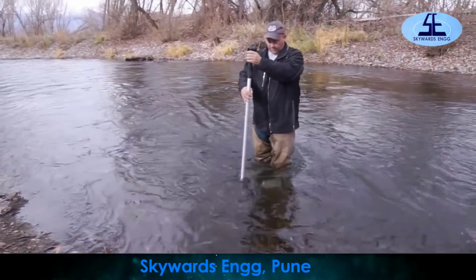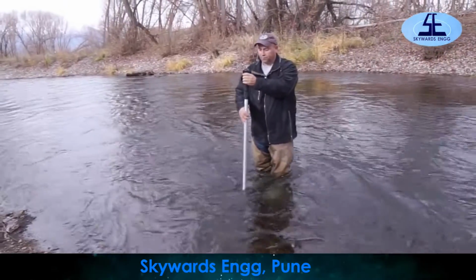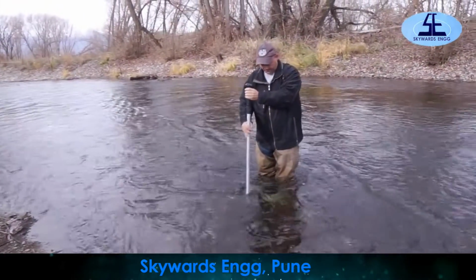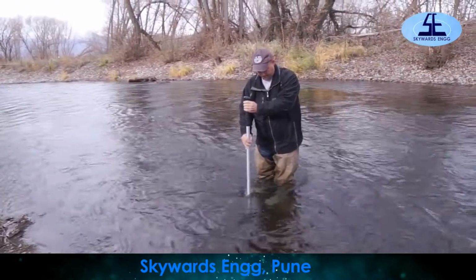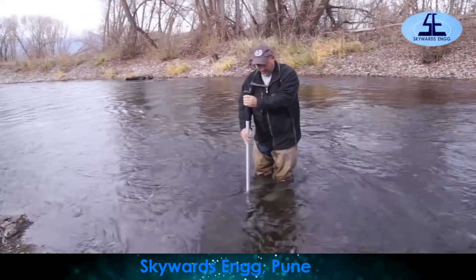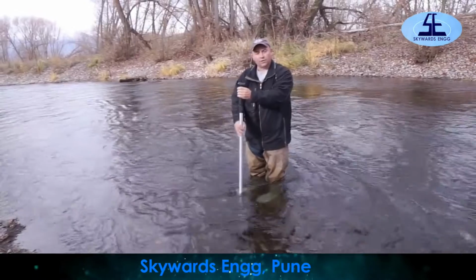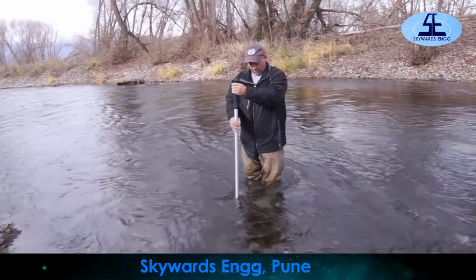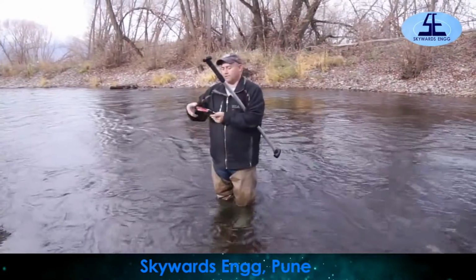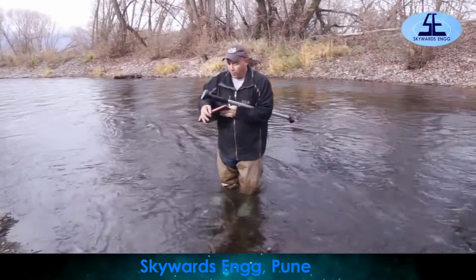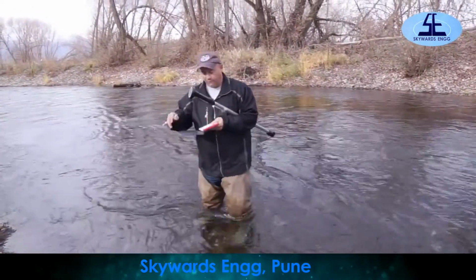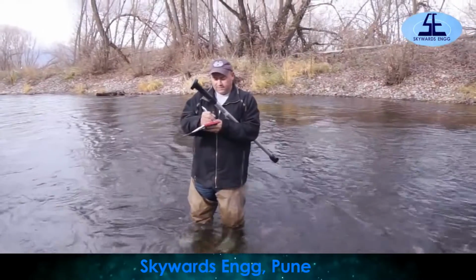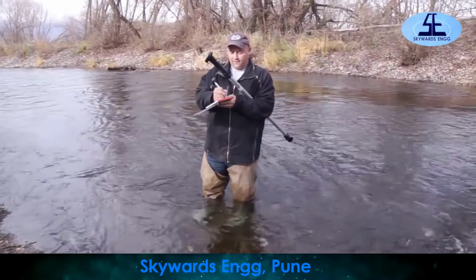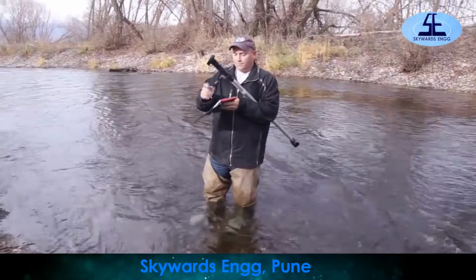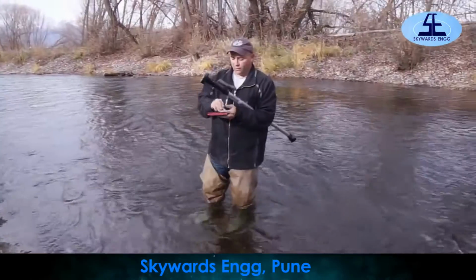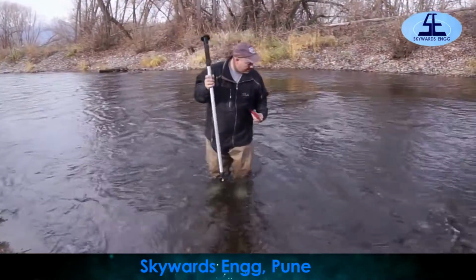and then I'll slowly have the probe descend to the bottom, and then bring it back up in a slow and controlled manner. Okay, so we measured at this point approximately a couple feet in from the side, a velocity average of 1.8 feet per second. So I'm just going to list those as I go across the channel.